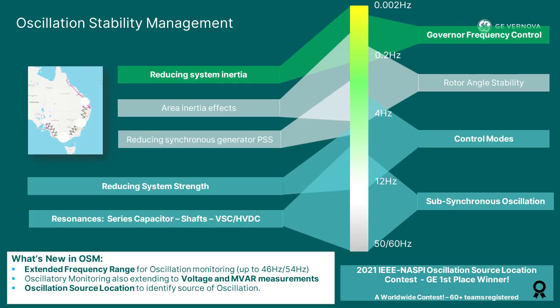Let's talk about oscillatory stability management. We've had that application in our portfolio for over a decade. However, what we've done is expanded the frequency of the dynamics that we can monitor. Typically, we've looked at the dynamics associated with conventional synchronous generation, so your thermal plants, your gas plants, and that's typically in the range of 0.2 hertz to 4 hertz. What we've done is expanded the range all the way to 50 or 60 hertz so that we can look at subsynchronous oscillations as well as oscillations associated with these inverter-based resources. Knowing that the inertia is dropping, on the lower side, we are able to look at governor control kinds of oscillations on the grids as well.